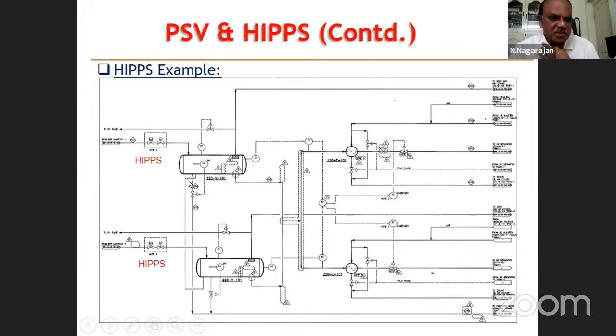High integrity pressure protection system, I told you, this is the inlet to the plant. HIPPS, high integrity pressure protection, is nothing but two valves together. Even if one valve fails, the other one will take care. That's why we have put two valves, and they will shut down. They will close in the event of sensing high pressure in the inlet stream. So this is called the HIP system. There are two trains, that's why we have shown two HIPPS valves.